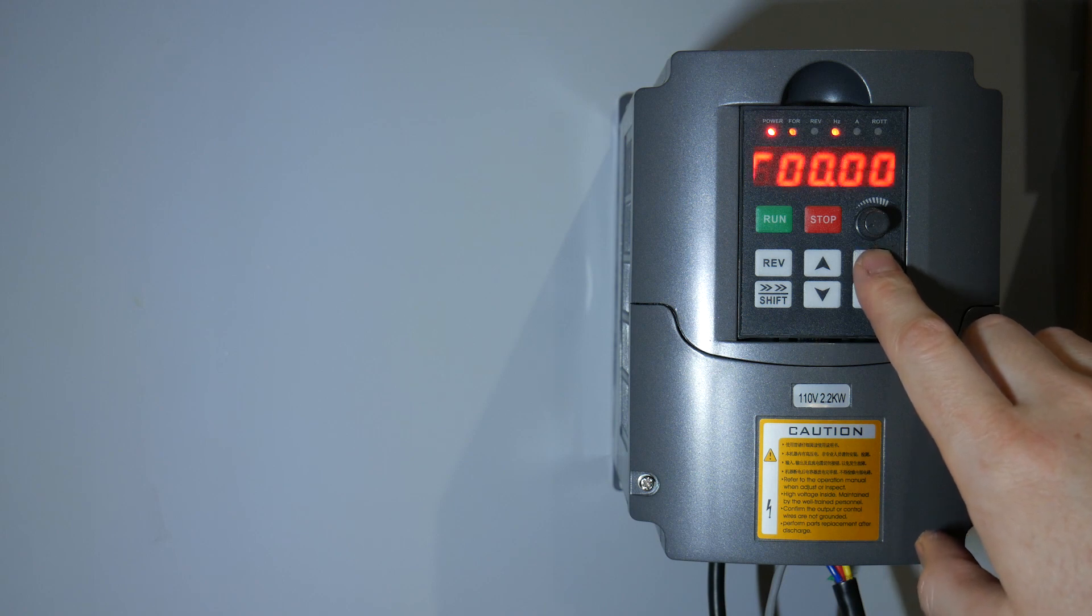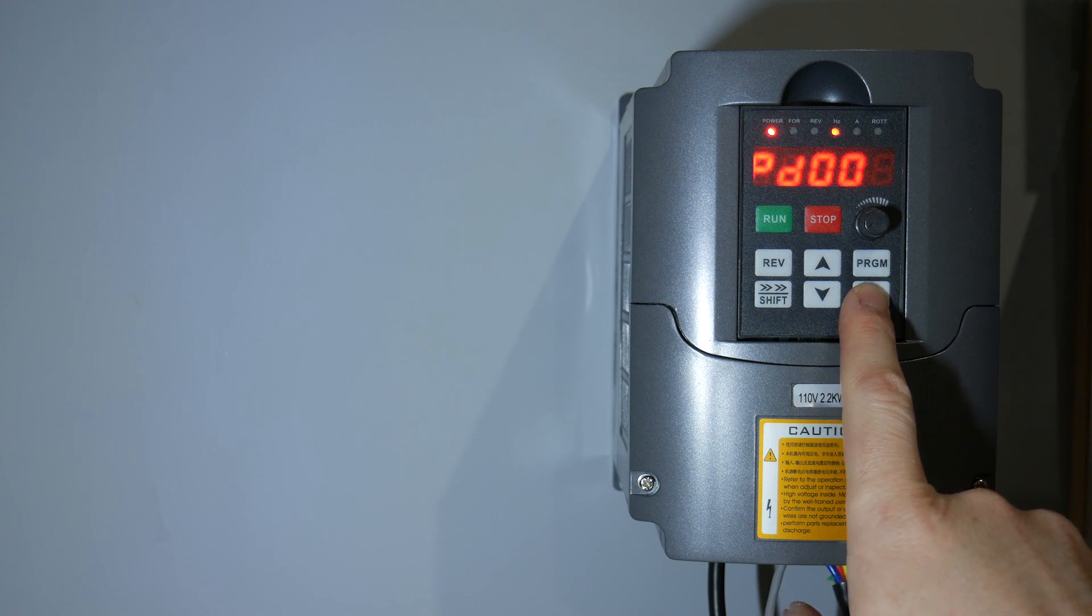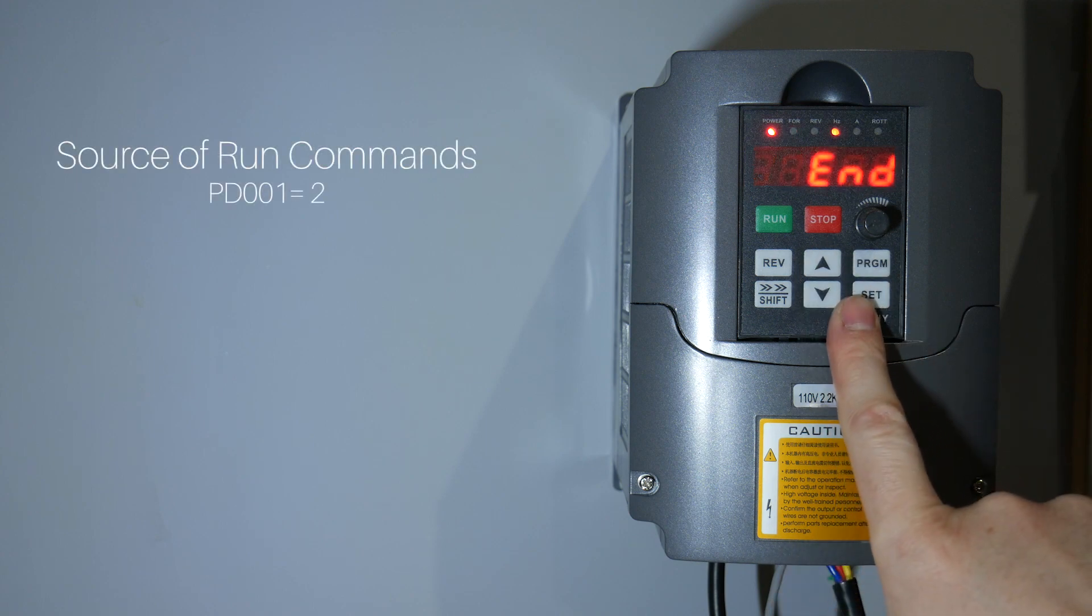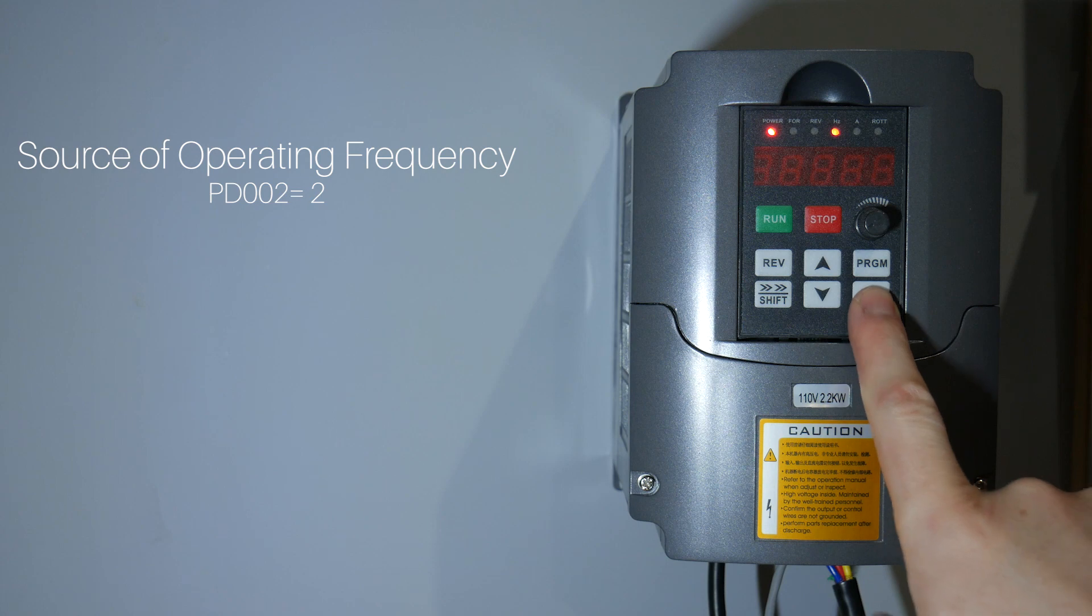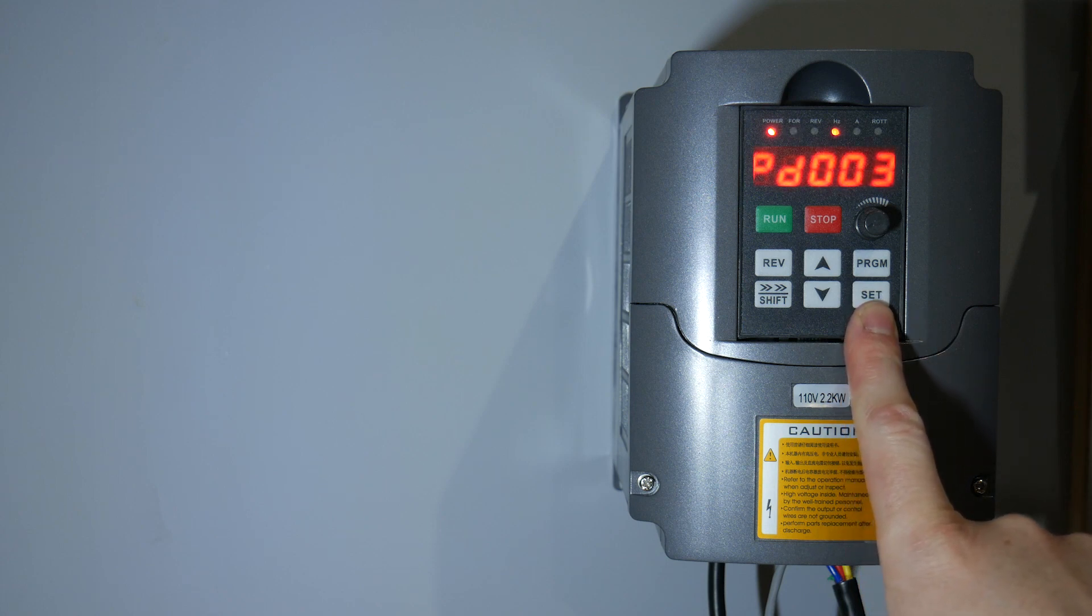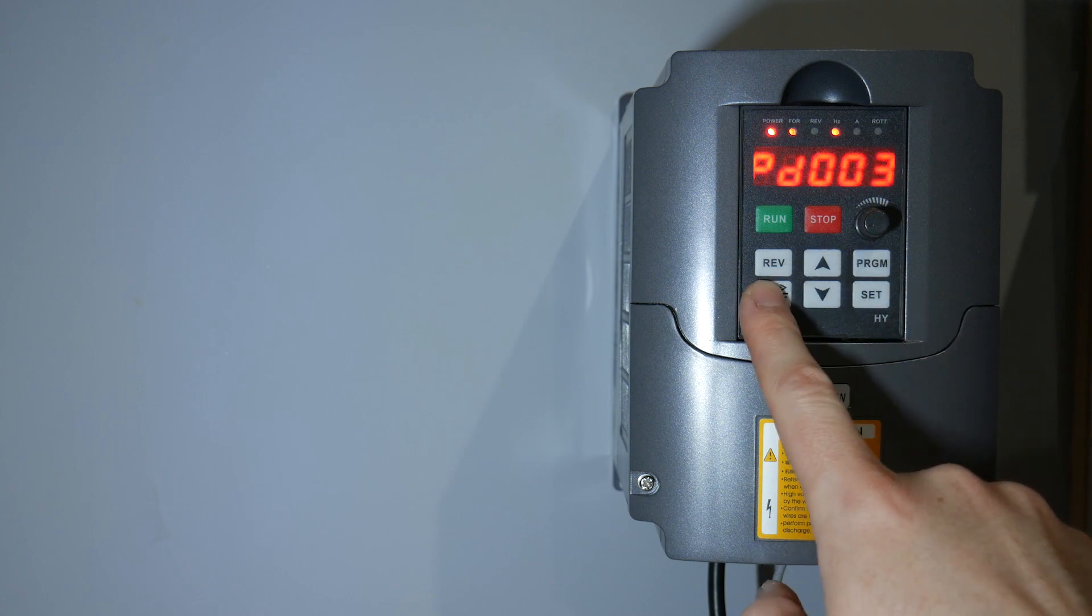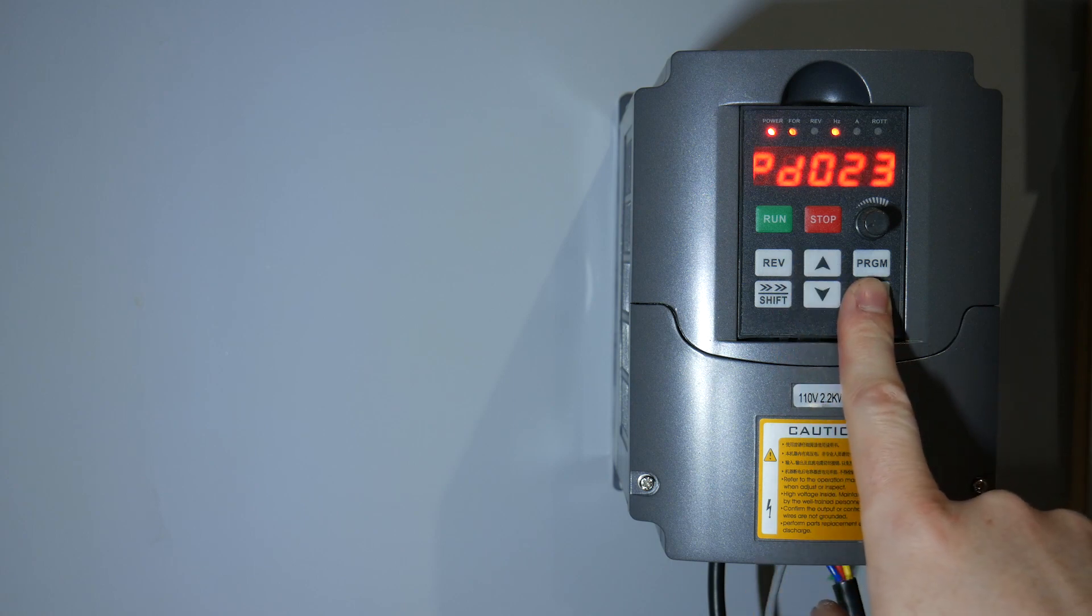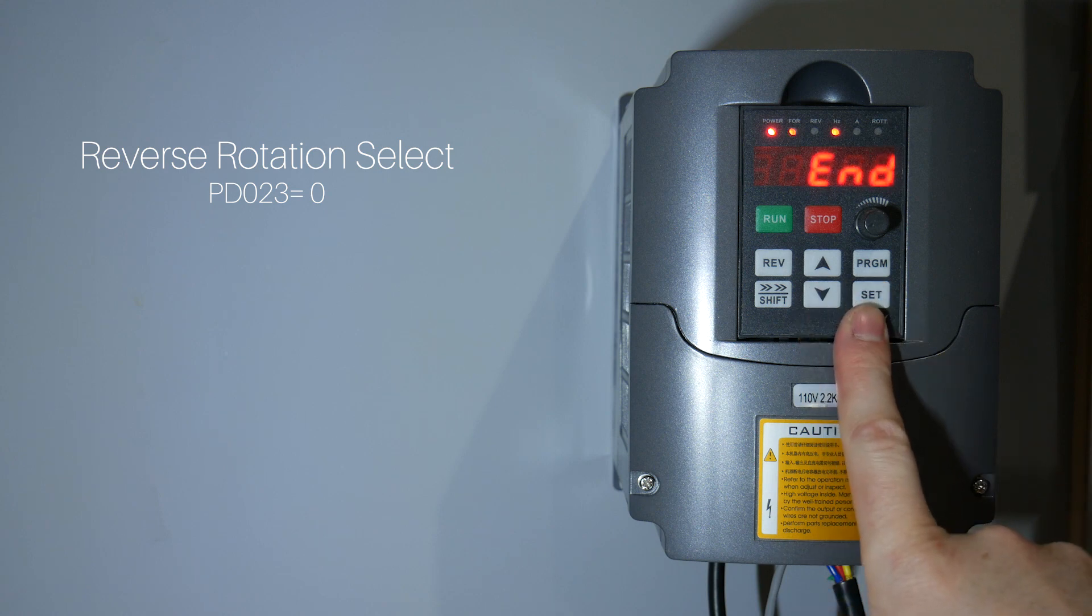Now we need to change the following settings. The source of run commands needs to be set to 2. The source of operating frequency also needs to be set to 2. Reverse rotation select should be set to 0 for disabled.